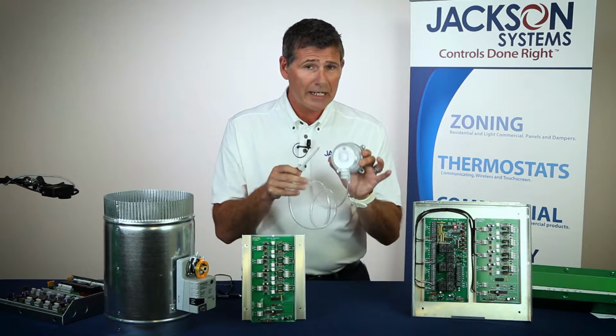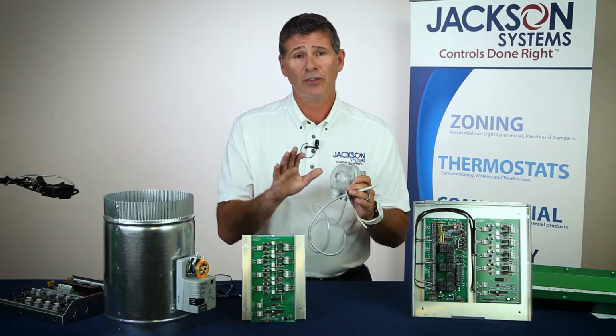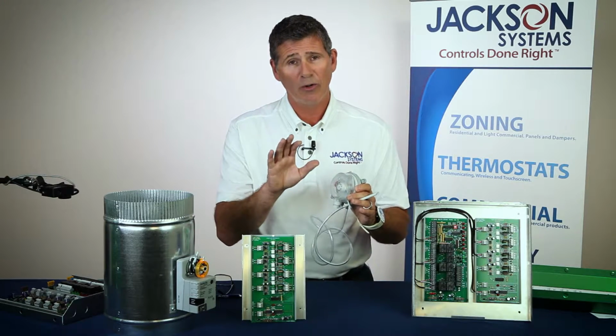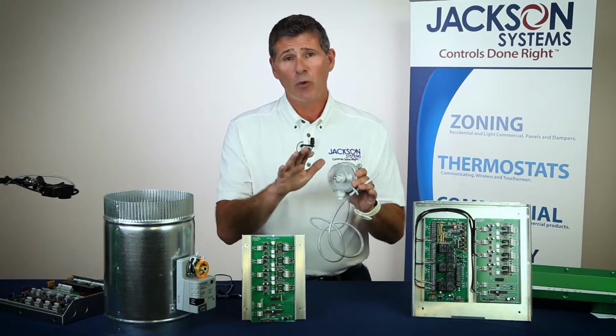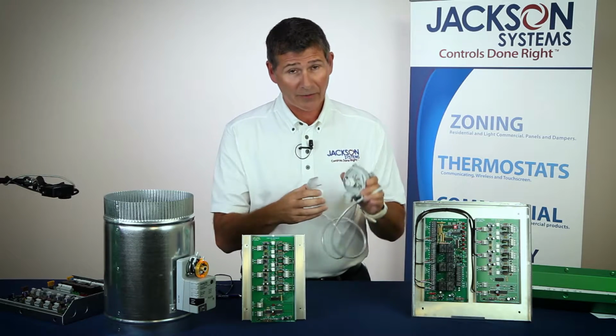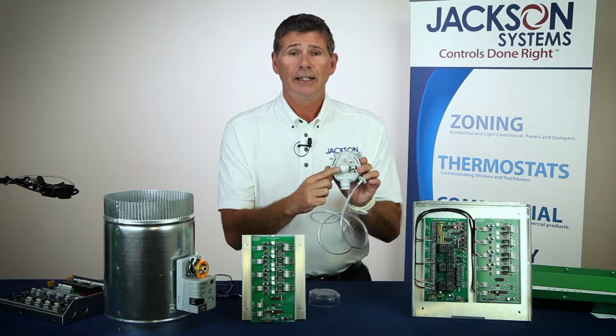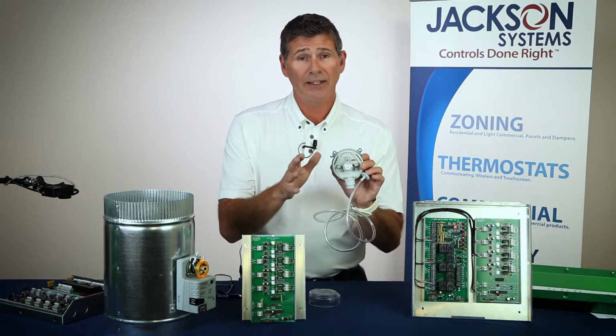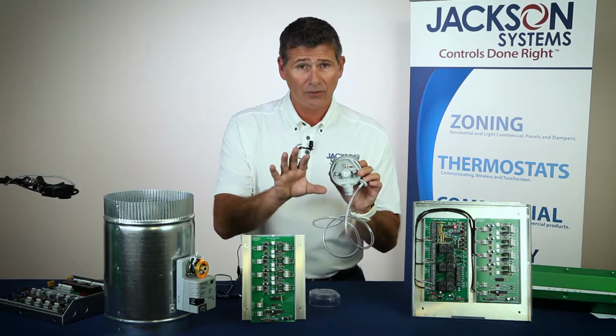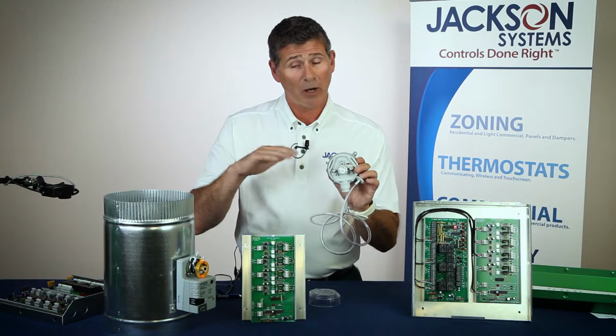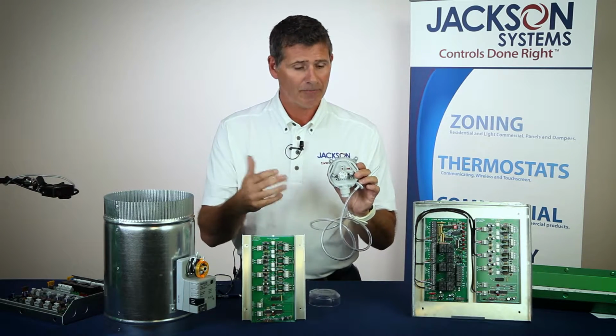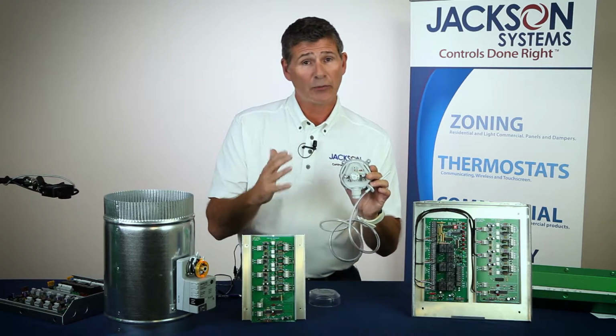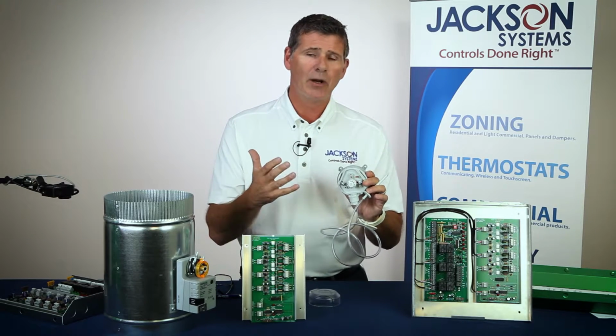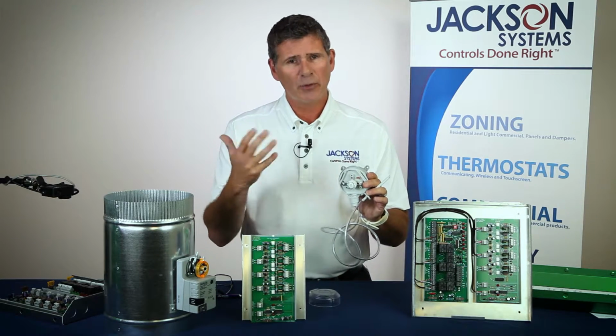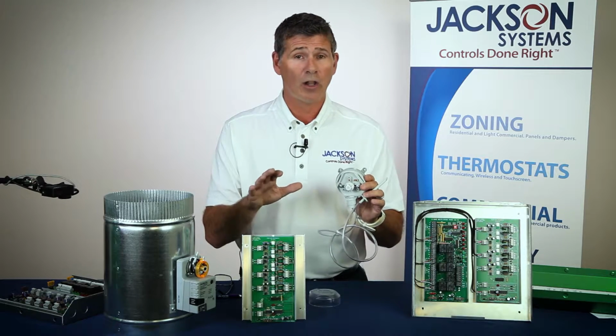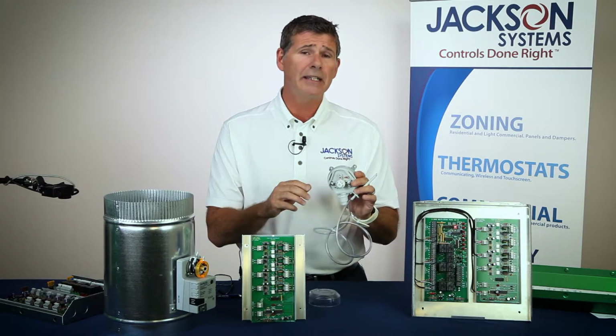And what's so unique about this is now you as the contractor, we're actually going to give you complete control on how much static pressure you want to go ahead and set the system up for. So on the inside of this, we've got a dial. And this dial is going to allow you to dial in the static pressure that you need for that system in order to get the dampers to modulate open to relieve that static pressure. It's going to come set at the factory at 0.35 inches of water column, and we do that primarily because we have found that 0.3 to 0.35 inches of water column worth of static pressure, that's when systems begin to get noisy.